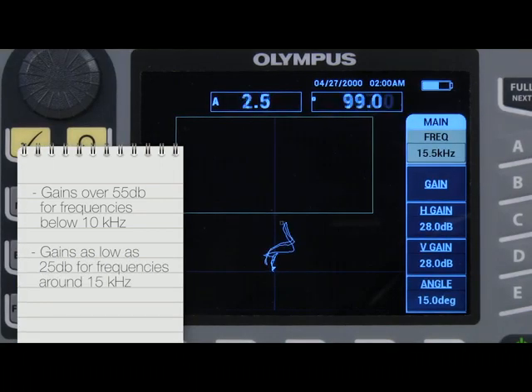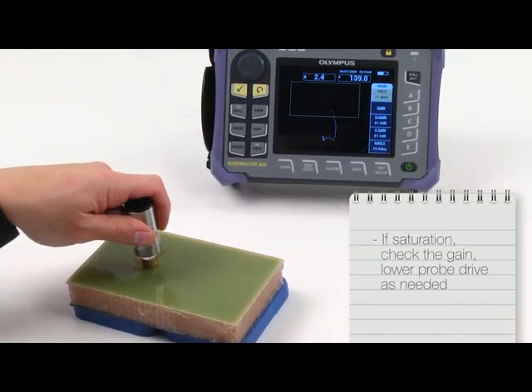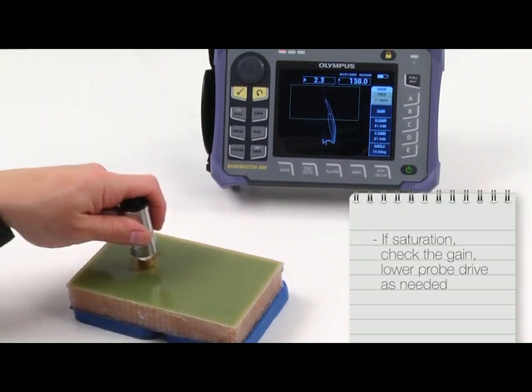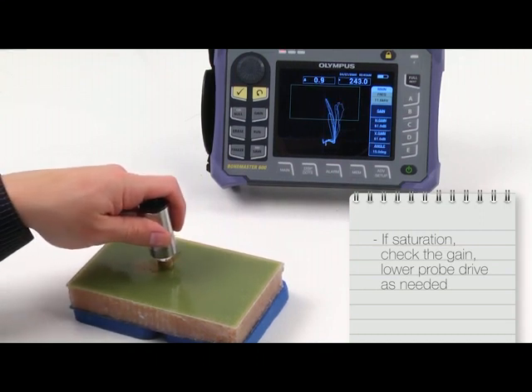Be aware that gains over 55 dB may be needed at frequencies below 10 kHz, but gains as low as 25 dB may be required at frequencies around 15 kHz. In summary, if you observe or suspect saturation, remember to check the gain and possibly lower the probe drive as needed.